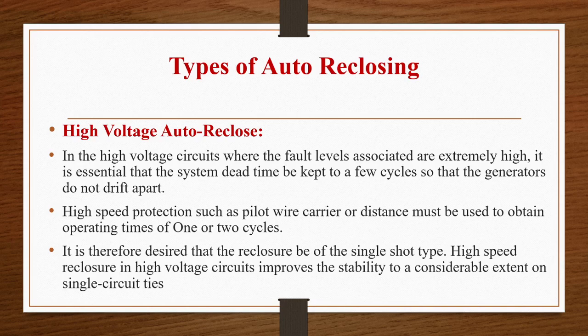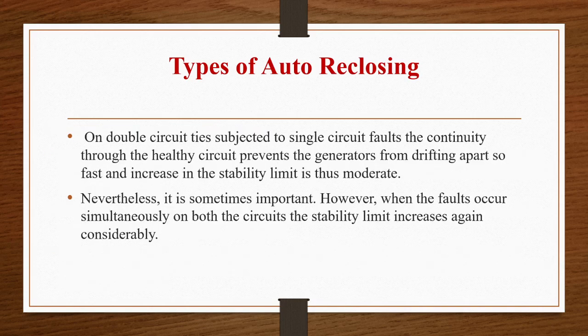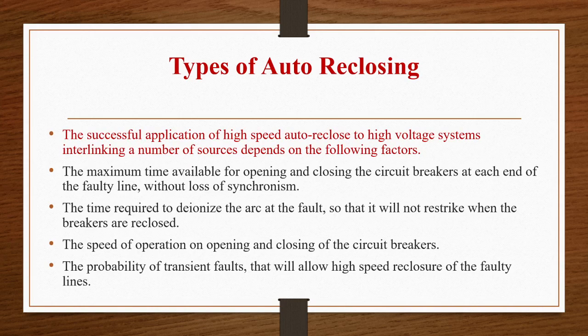High speed reclosure in high voltage circuits will improve the stability to a considerable extent on single circuit ties. Now on double circuit ties subjected to single circuit faults, continuity through the healthy circuit will prevent the generators from drifting apart so fast, and the increase in the stability limit is thus moderate. However, when faults occur simultaneously on both the circuits, the stability limit will increase again considerably.